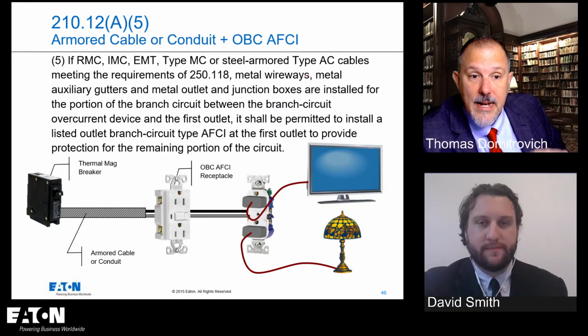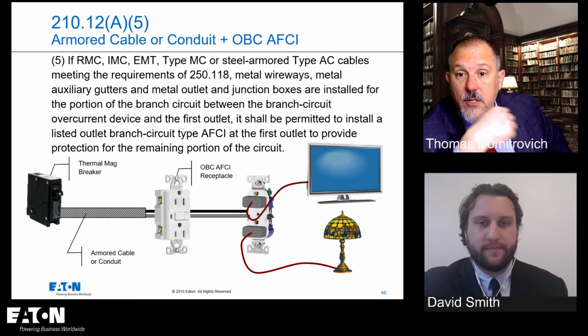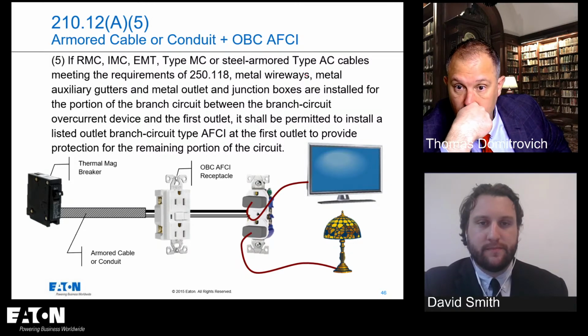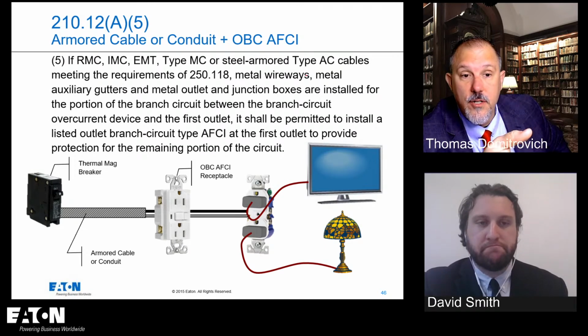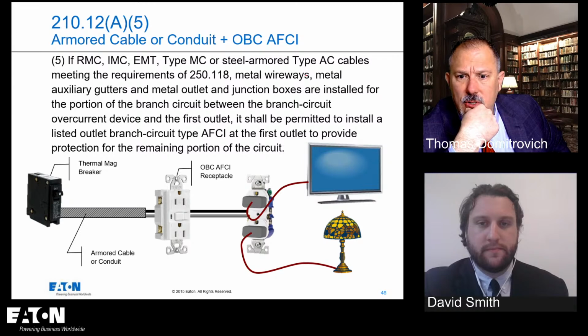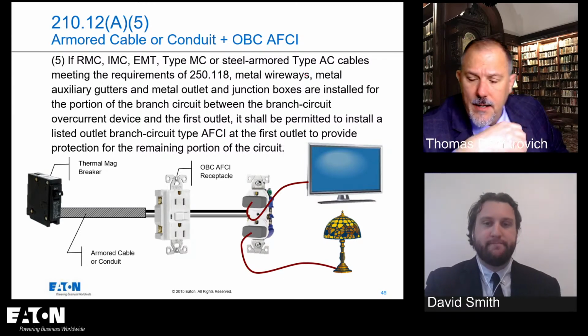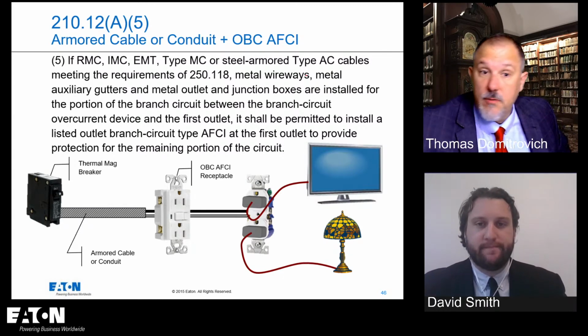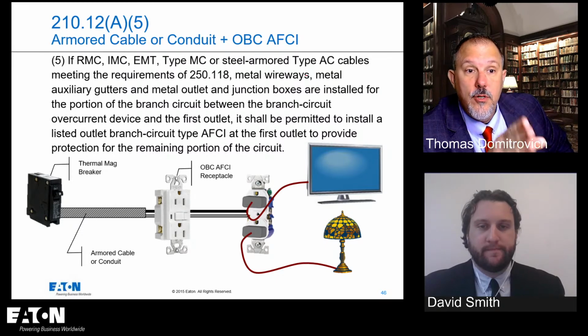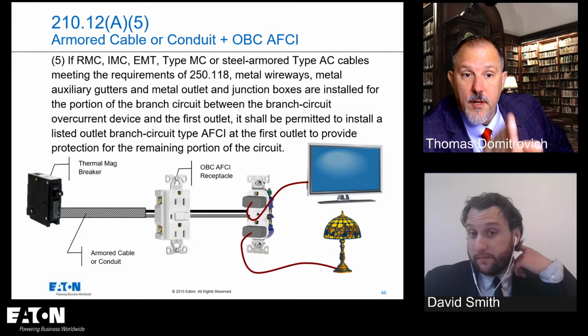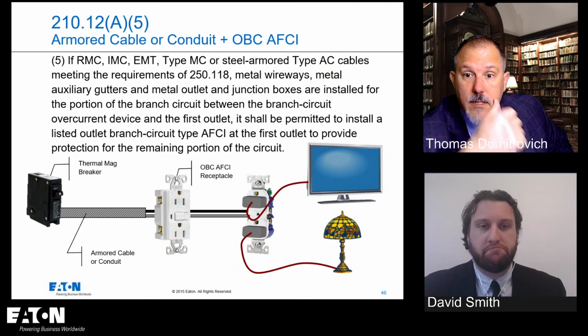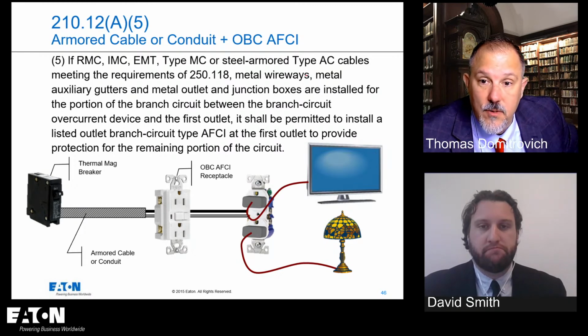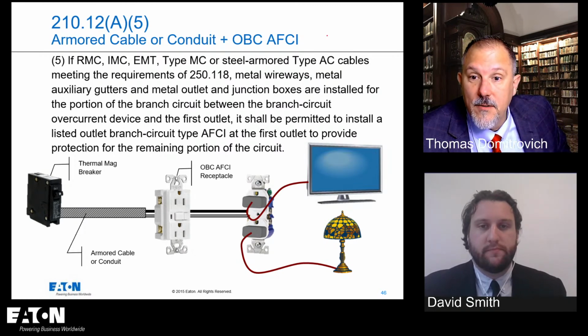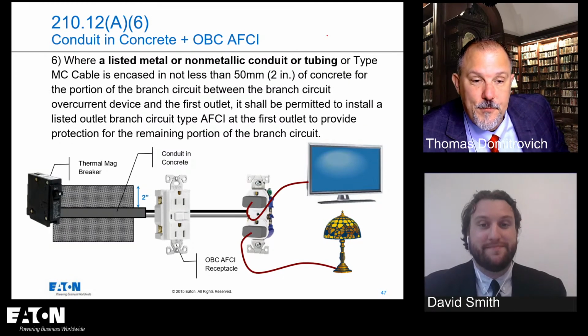So if you provide that level of protection, and you know where they do this a lot? Chicago. Is it really? Yeah, Chicago is all in. I think it's rigid metal conduit. I think they use a conduit up there. Wow. Yeah, and that's part of the building code. So technically, you could use a standard thermomagnetic breaker with an OBC in those Chicago markets. That's the first place that my guys are. You should be up there talking about it with those guys.